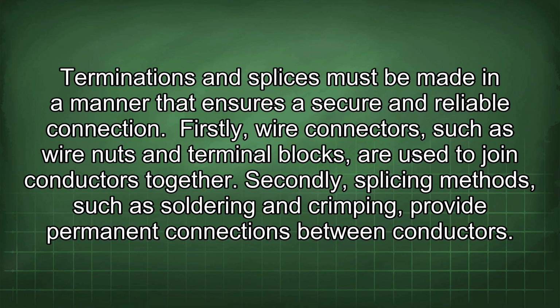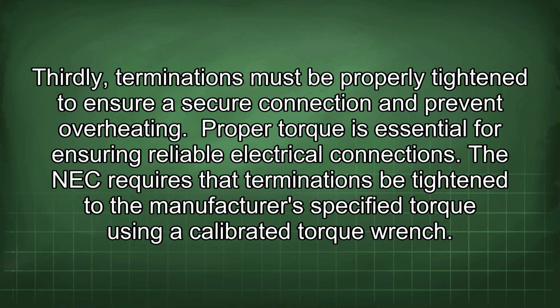Firstly, wire connectors, such as wire nuts and terminal blocks, are used to join conductors together. Secondly, splicing methods, such as soldering and crimping, provide permanent connections between conductors. Thirdly, terminations must be properly tightened to ensure a secure connection and prevent overheating. Proper torque is essential for ensuring reliable electrical connections.